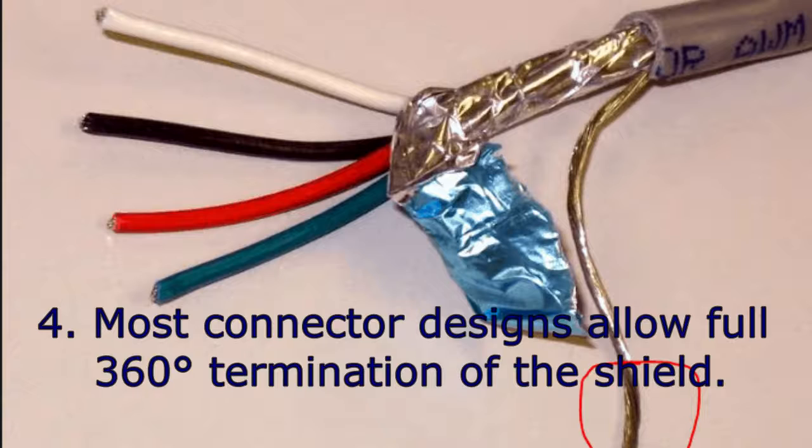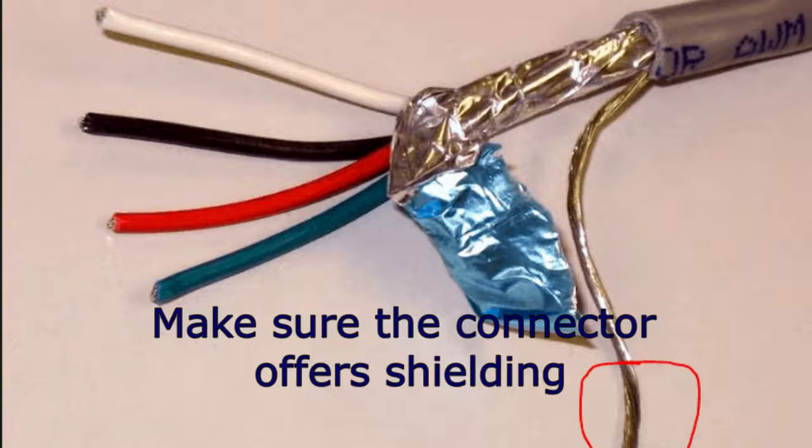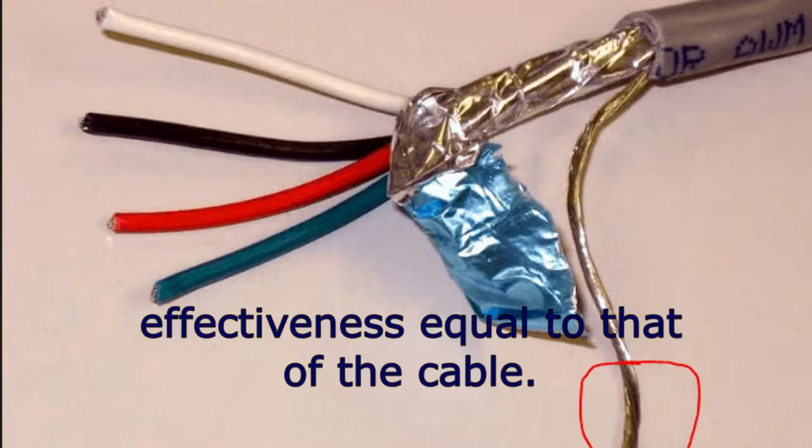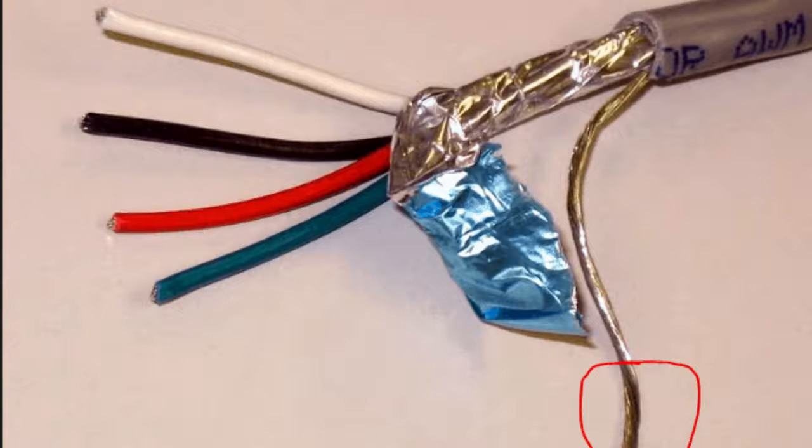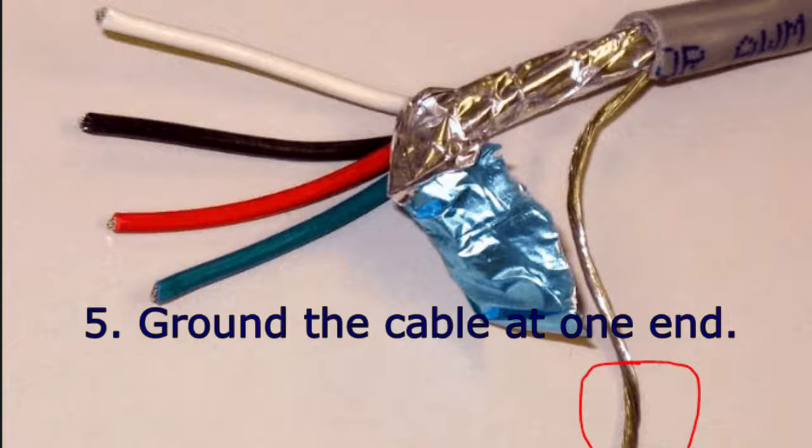Four, most connector designs allow full 360-degree termination of the shield. Make sure the connector offers shielding effectiveness equal to that of the cable. For example, many common connectors are offered with metal-coated plastic, cast zinc, or aluminum backshells. Avoid both over-specifying and paying for more than you need, or under-specifying and getting poor shielding performance.